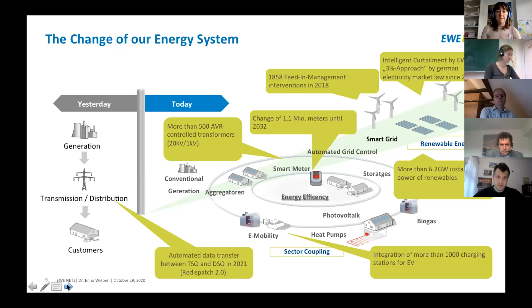Today we have installed around about 500 AVR controlled transformers between the 1 kV level and the 20 kV level, because in distribution medium voltage grids and low voltage grids with a lot of solar power and wind power, we have problems and challenges concerning voltage levels and voltage control.